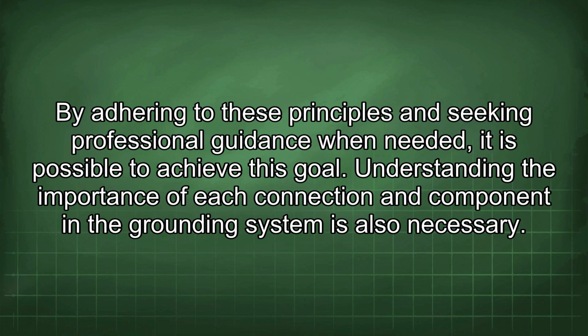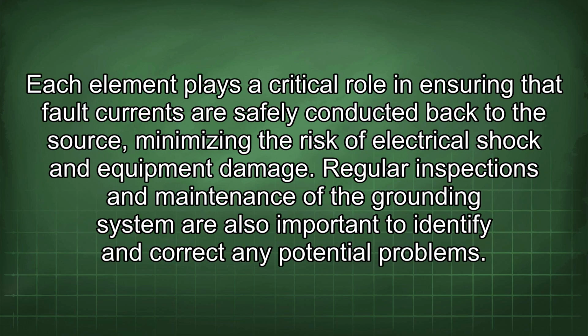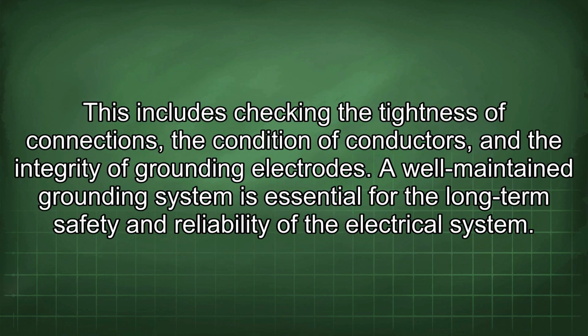Understanding the importance of each connection and component in the grounding system is also necessary. Each element plays a critical role in ensuring that fault currents are safely conducted back to the source, minimizing the risk of electrical shock and equipment damage. Regular inspections and maintenance of the grounding system are also important to identify and correct any potential problems. This includes checking the tightness of connections, the condition of conductors, and the integrity of grounding electrodes. A well-maintained grounding system is essential for the long-term safety and reliability of the electrical system.